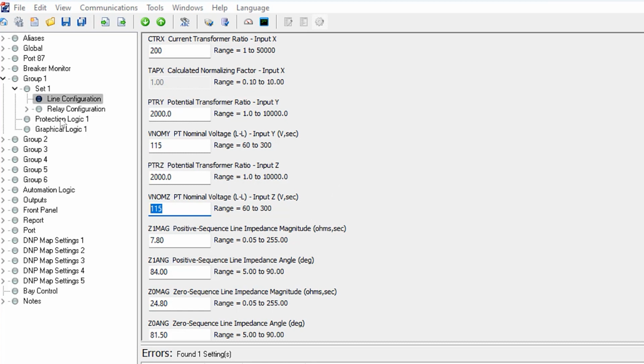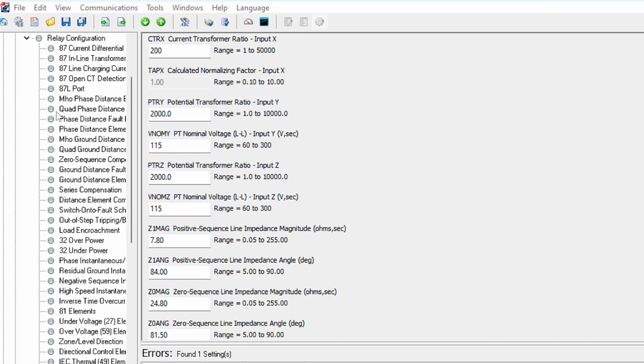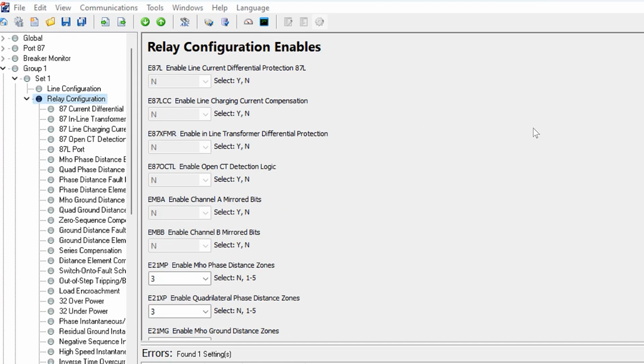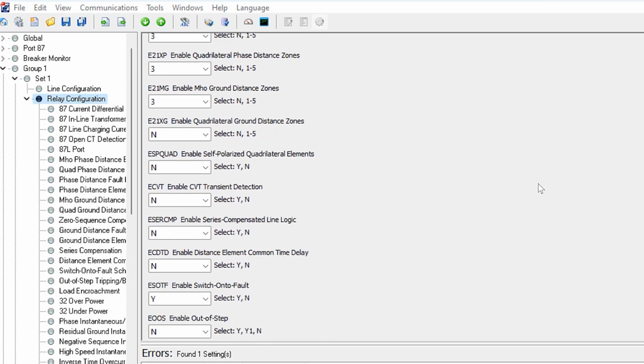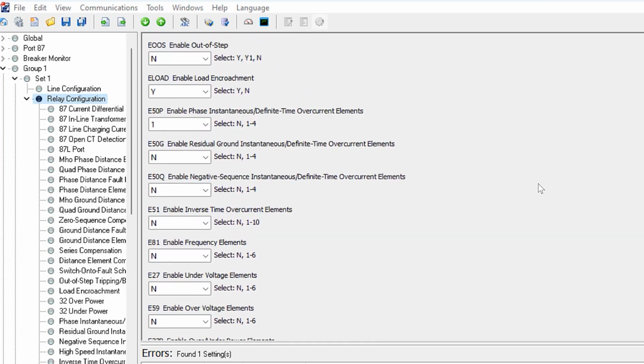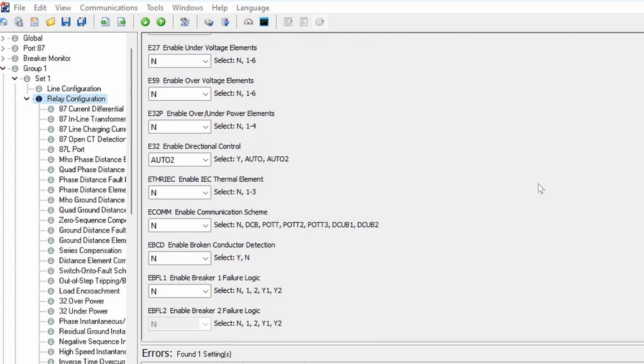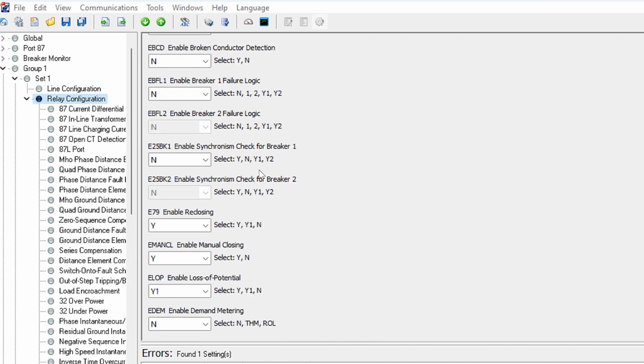All right, then we need to enable the sync check function, so we can go to relay configuration over here. And this is where you set your enables. So basically all the elements that you're going to be using in your settings. We can scroll down over here to the sync check element, and that's over here. And we can see that we have breaker 1, breaker 2.